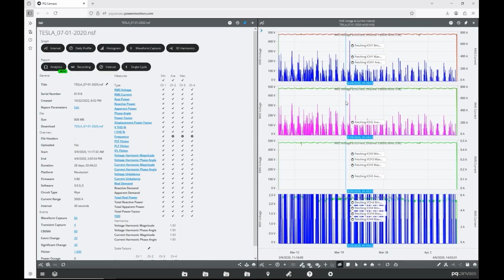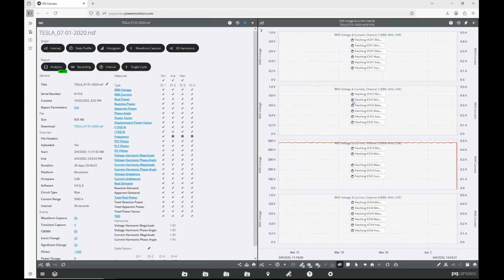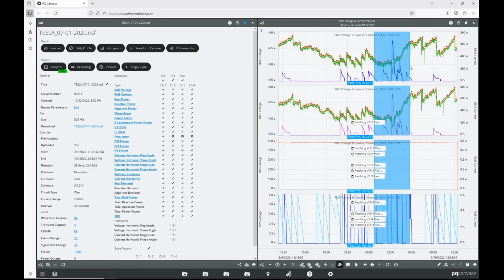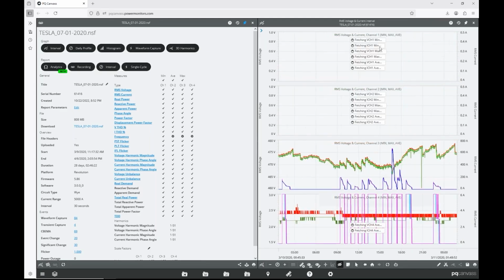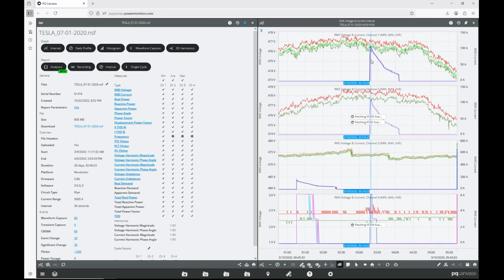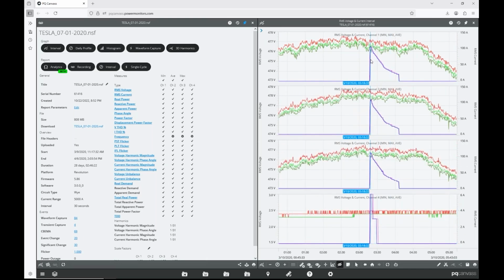But occasionally you'll see, for example, here, the maximum current is when we happen to have a lot of cars. This is the highest current in the entire recording. Here we're seeing much higher current than the others. This is multiple cars at a very fast charge. Yeah, no waveform triggered, so that did not affect the voltage much. You can see there's no minimum voltage change. So this is a stiff system here.